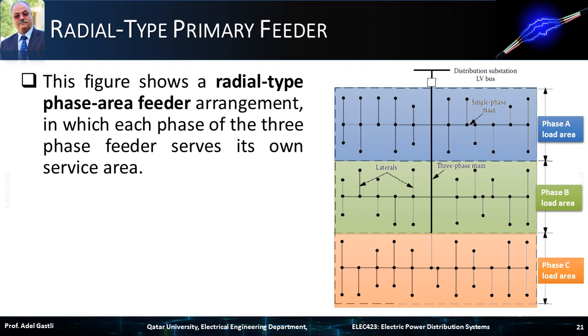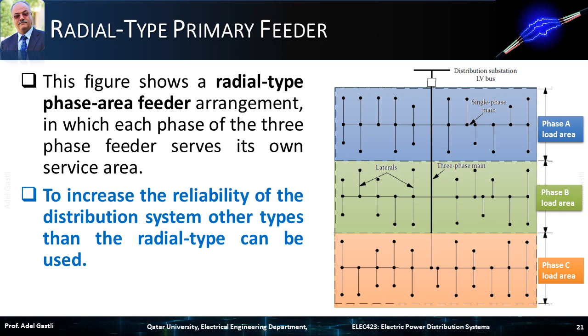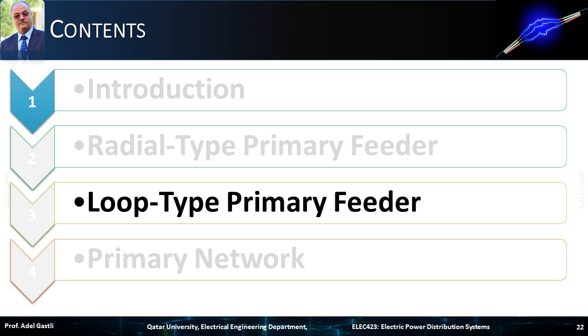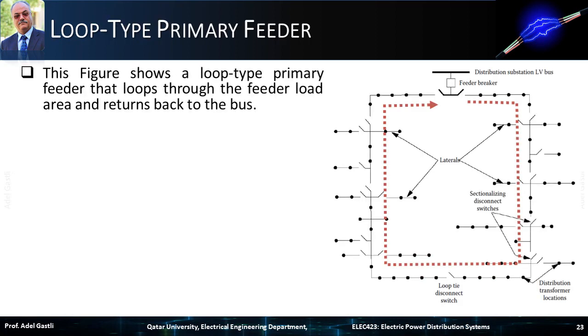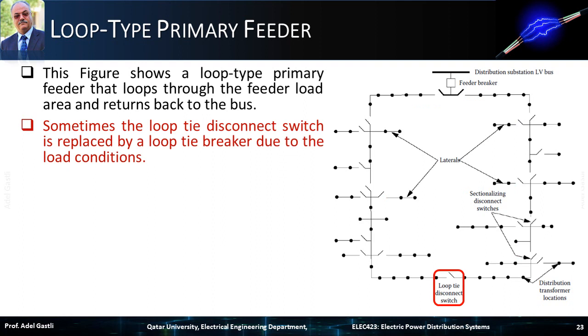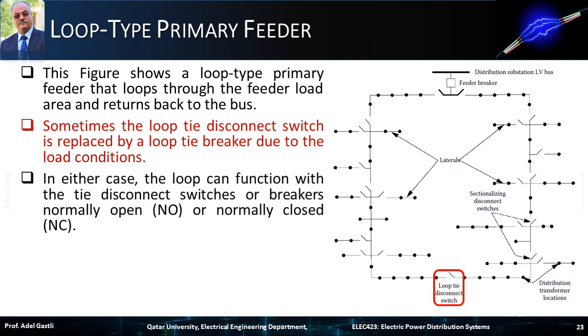To increase the reliability of the distribution system, other types than the radial type can be used. For instance, the loop type primary feeder is more reliable than the previous radial types. This figure shows a loop type primary feeder that loops through the feeder load area and returns back to the bus. Sometimes the loop tie disconnect switch is replaced by a loop tie breaker due to load conditions. In either case, the loop can function with the tie disconnect switches or breakers normally open (NO) or normally closed (NC).